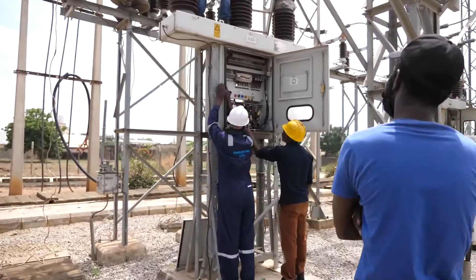We are going to carry out a series of tests on the transformer today. We have ratio, short circuit, core balance, and the IR. When we do all this, we go back to the factory test or the pre-commissioning test and see whether it is the same or whether there's a deviation. If there's any difference, we try to see what causes it, then we try to arrest it. That's the aim of annual maintenance: to see if your equipment is degrading, and what action you are to take before final breakdown. That's the main reason why we do this annual maintenance.